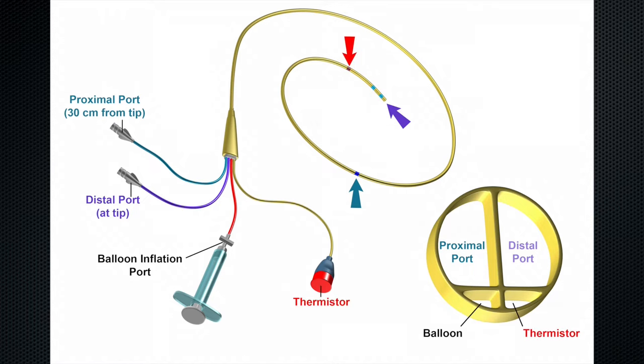The final lumen in this pulmonary artery catheter is used for the thermistor. The thermistor is an external coil on the catheter approximately 4 cm from the distal tip. It is used to measure core blood temperature within the pulmonary artery and is a key tool in the measurement of cardiac output by the thermodilution method.